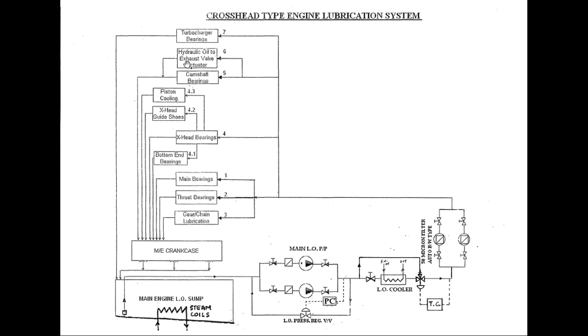The lube oil sump is not an integral part of the bed plate but is part of the ship structure, normally provided in the double bottom space. The sump is surrounded by a cofferdam on all sides to prevent contamination of lube oil from surrounding tanks in case any sump boundary develops a leak. The lube oil sump is provided with vents with flame traps, and has a sloped bottom with the lube oil purifier suction located at the lowest end.